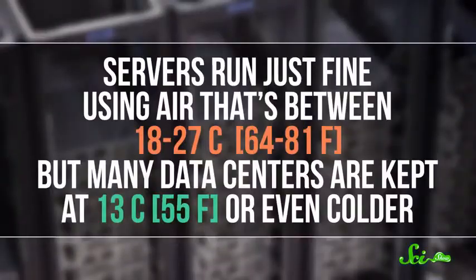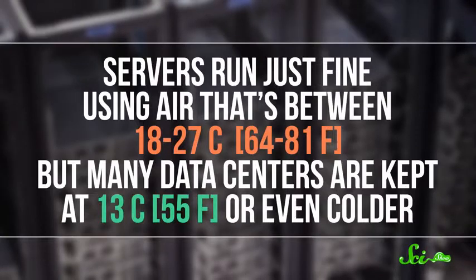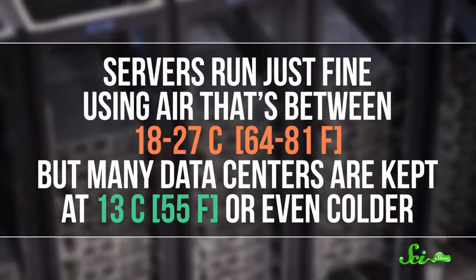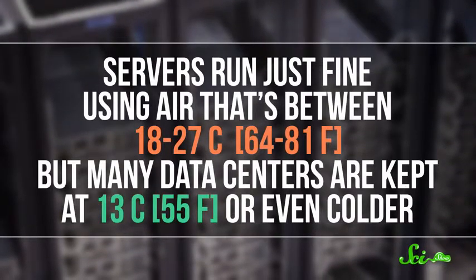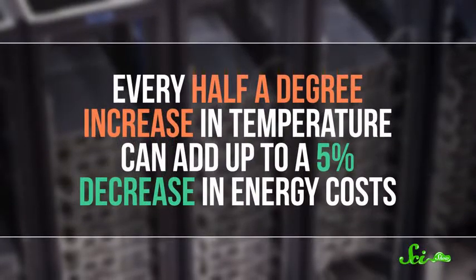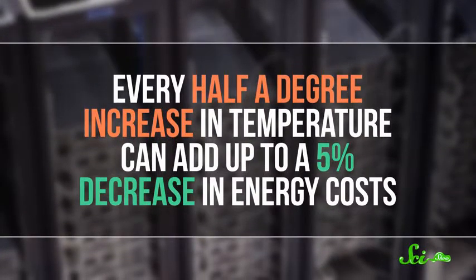You can also cut the amount of electricity that air conditioning uses by actually raising the temperature. Servers run just fine using air that's between 18 and 27 degrees, but many data centers are kept at 13 degrees or even colder. Every half a degree increase in temperature can add up to a 5% decrease in energy costs. So while a 27 degree room might be a little toasty for some people, there's no reason we can't just raise the temperature in the room and save a lot of energy.